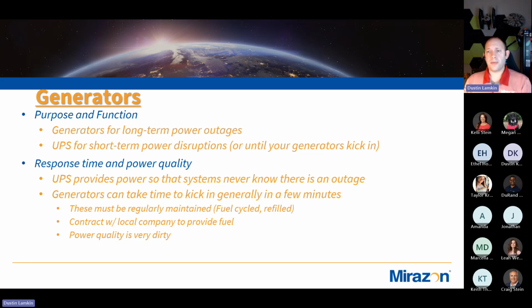Generators are great though, they provide that mains power where your UPS can't hold it. But they do need to be maintained, we've got to cycle that fuel. If they're running on diesel, we need to make sure we get it maintained regularly, monthly, quarterly, and run it, we have to cycle the fuel - if it sits for too long it goes bad, so we need to make sure we're taking care of it. If it's on a consumption-based fuel, propane or diesel, we need to make sure we have a contract with somebody.